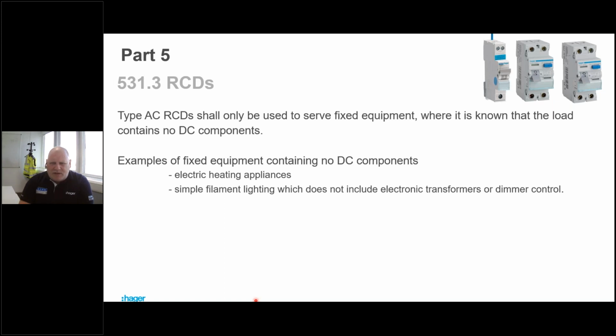That's quite difficult really, because they gave us a couple of examples here. They've put electric heating appliances, but if you put a timer on that heating appliance, we've got DC components in that timer. Simple filament lighting, but if we've got electronic transformers or dimmer control, again, that's out the window. So we've got to use a type A RCD now for most installations.